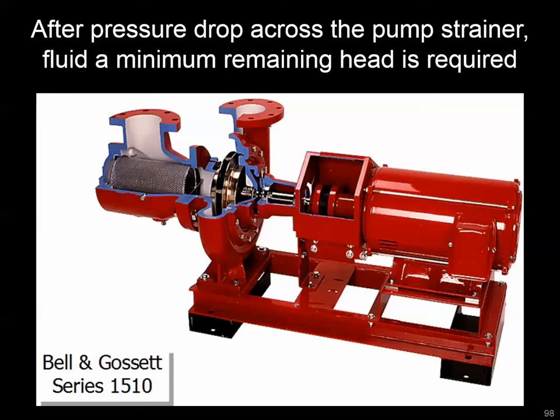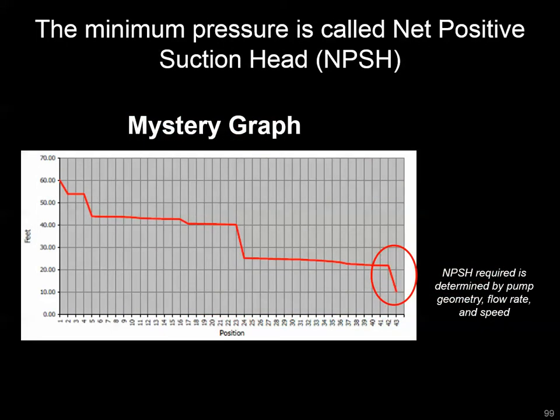Here's what that strainer device looks like at the inlet of a centrifugal pump — it's part of a suction diffuser. Once you discharge from the suction diffuser and leave the strainer, there's a minimum head or minimum pressure you need going into the pump, or you might have a situation called cavitation. As we discussed with our pressure gradient, you leave the pump at a certain head and at each incremental pressure drop you're gradually losing pressure. Right at the suction diffuser, pump manufacturers require for a specific flow that you have a minimum amount of pressure — called the net positive suction head required (NPSHR) — in order to prevent cavitation.